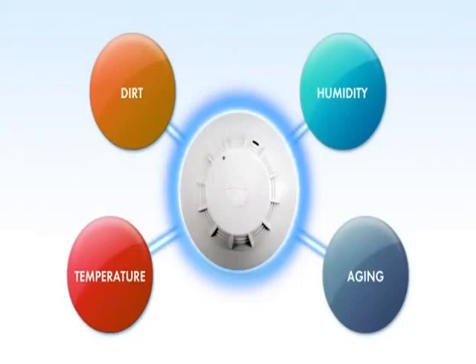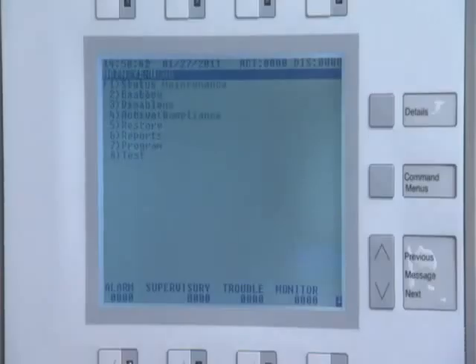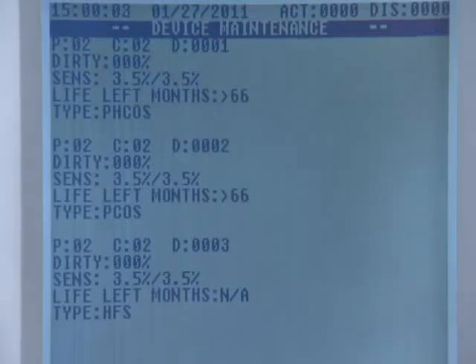For optimum performance, Signature Series detectors automatically adjust for dirt, humidity, temperature, aging, and other environmental factors, which are responsible for the majority of unwarranted alarms. The devices now, with their technology, can not only adapt to their own environment, but can also assess the environmental changes. All detectors can transmit a sensitivity measurement and percent dirty level back to the control panel, which can be viewed on the LCD display or printed. This feature eliminates the need to measure the unit with a special calibrated test instrument and perform unnecessary detector cleaning, resulting in another significant cost savings.